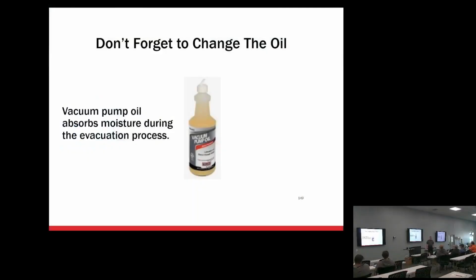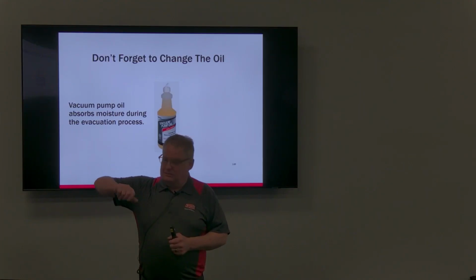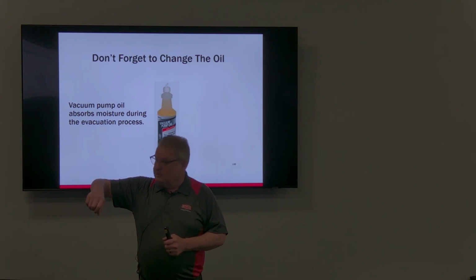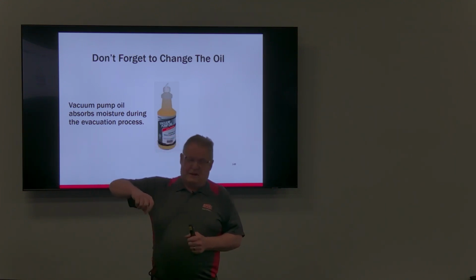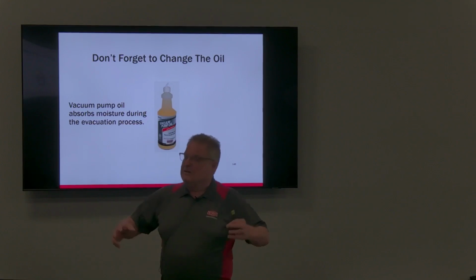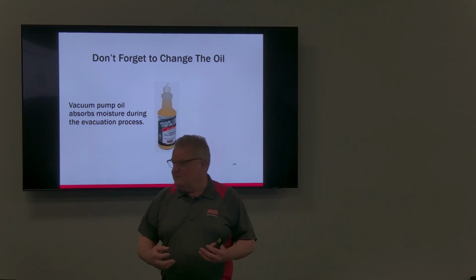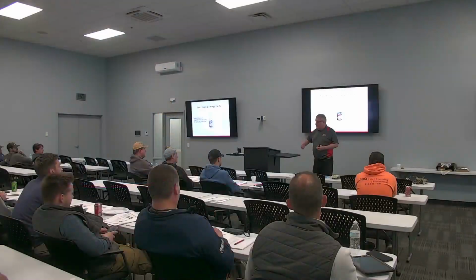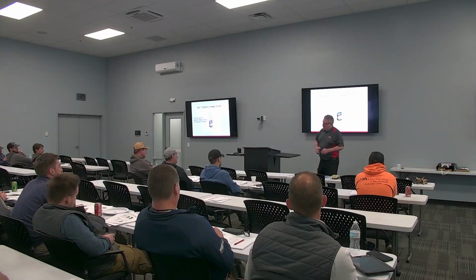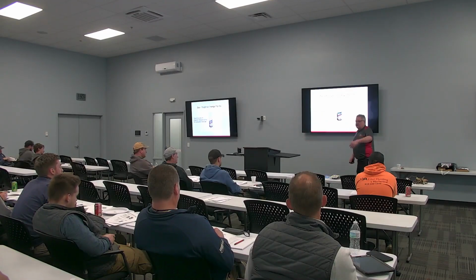Vacuum pump oil. And this sounds like something silly to tell you, but you need to change your vacuum pump oil. All right. And I know most of you work for somebody else, the boss is paying for it. No, honestly. The moisture that comes out of that system goes into the oil. Is everybody familiar with that little bleed ballast port on your pump? Do you all know what that's there for? You should leave that open until you're down about 20 inches, because all that big gush of moisture that comes out first, that's what that port is for, to allow it to escape the pump without putting it into the oil. So open that ballast port. That keeps the oil dry.